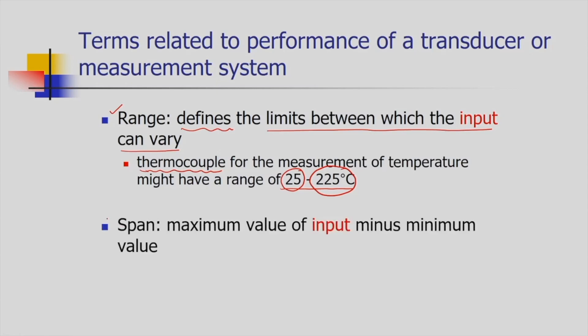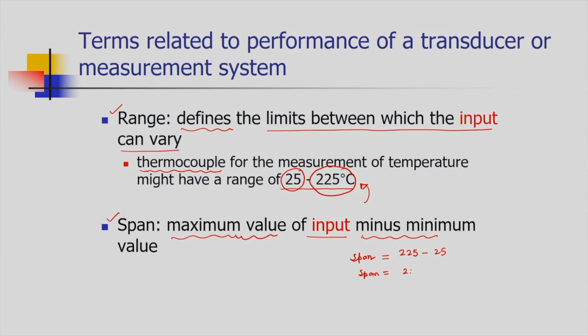The next term is span. Span is nothing but the difference between the maximum value and the minimum value of the input. Taking the same thermocouple example, the span is 225 minus 25, so the span is 200 degree Celsius.